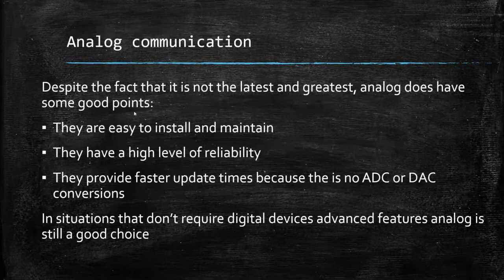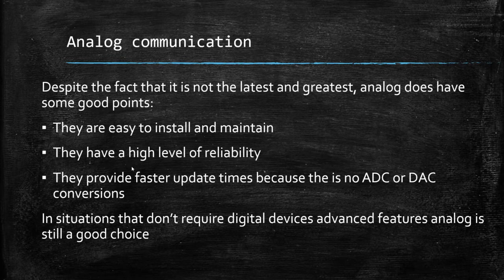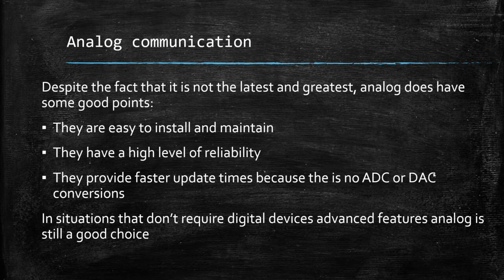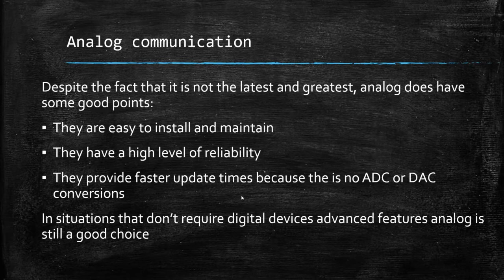Analog communication, despite the fact that it's not the latest and greatest, still has some good points. They are easy to install and maintain — shielded twisted pair is nice, and as long as you can strip some wire and tighten some screws, it's not a big deal. They have a very high level of reliability and provide faster update times. This is probably the biggest significant difference between analog and digital in the context of the ILM. Analog devices are faster because the signal does not have to be converted from analog to digital for processing and then back to analog. Analog is just analog — no conversions at all. So in situations that don't require the advanced features that digital devices have, analog is still a good device.